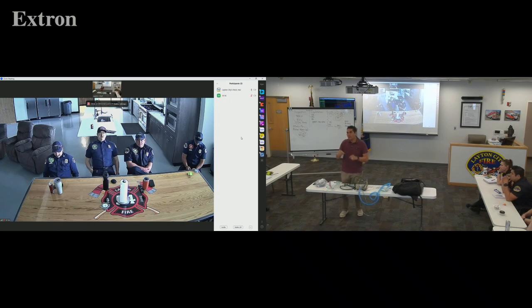Time and time and time again, people keep moving from pressure control to volume control, but then they don't move alarms. And so this ventilator would be alarming because you have a peak pressure of, let's say, 35, and your peak pressure alarm is 32. Do you guys know what an alarm is on a ventilator? What is the purpose of the alarm? Get your attention. It's more than get your attention. It's actually a hard limit. So what you're telling the ventilator is that those alarms that you have there, the ventilator is not going to allow the patient to go any higher than that.